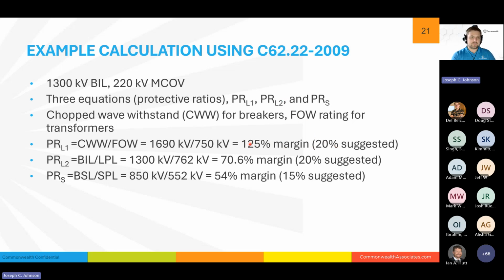So this is exceeded. Then for the protective ratio lightning 2, that is the BIL over the lightning protective level, which is your lightning impulse. So that is the 1300 kV divided by the 762 kV that we saw, 70.6% margin with 20% suggested. And then switching, the BSL over the switching protective level, which was that 2 kA 45/90 microsecond wave. That's 552 kV, 54% margin with a 15% suggested. So this is massively oversized from this perspective.